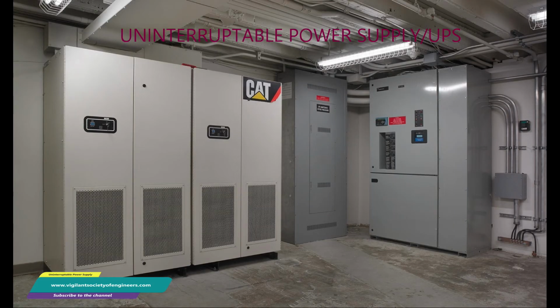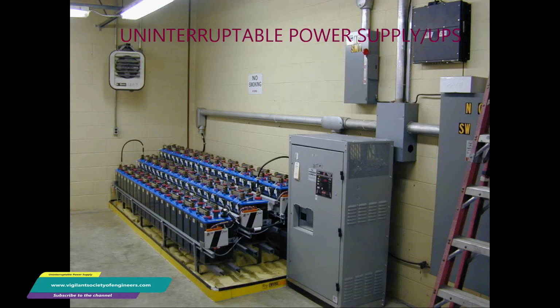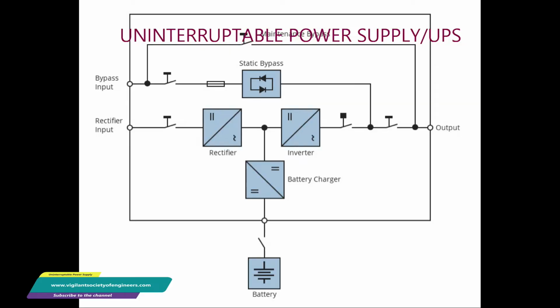By the external maintenance bypass circuit, more commonly, this is used when allowing the UPS system to be bypassed on a standby diesel generator power. When batteries are replaced or removed, this can only be done by placing the UPS supply into the external bypass.